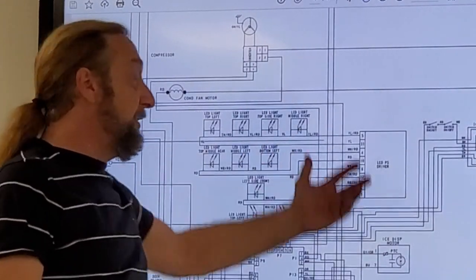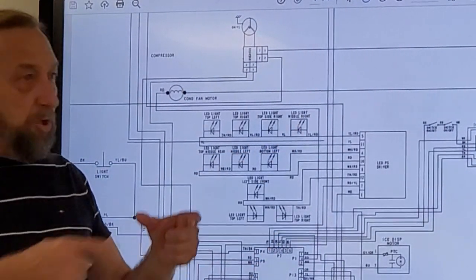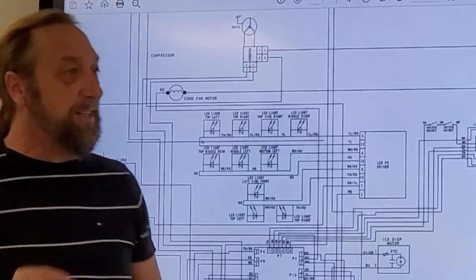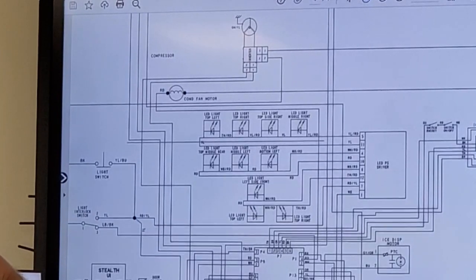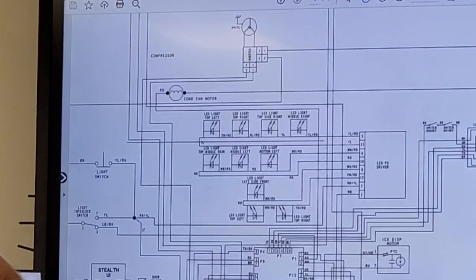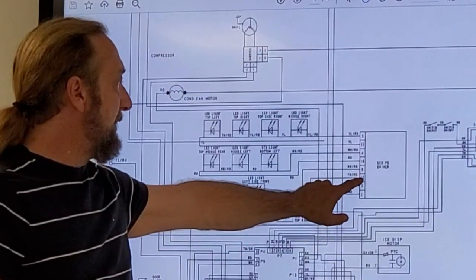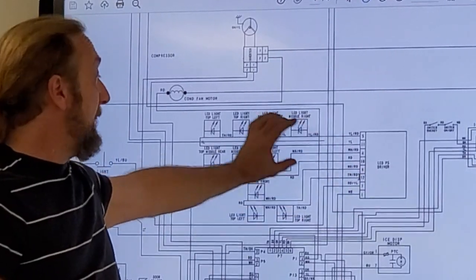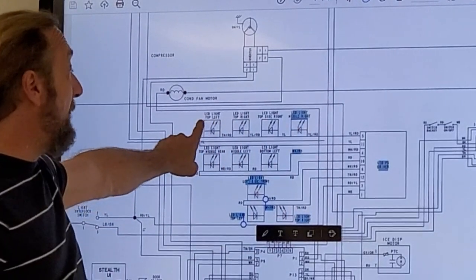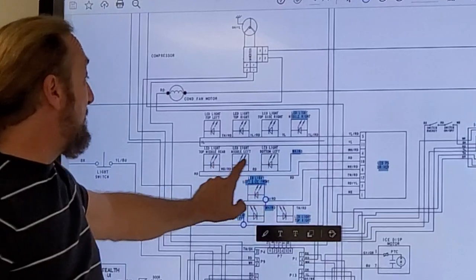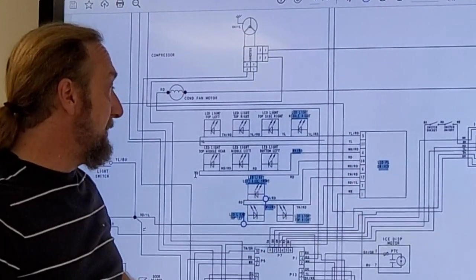So if you had no lights at all, you could have bad lights in one section. I've had customers sometimes where one light goes bad and they never call. Then another one goes bad in a different circuit, now they have no lights and they call for help. You're like, what are the odds of all those lights being bad — it's got to be a bad board, right? Or a door switch. So you go check for 120. I got 120 — okay, I'll order the driver board. So all we have to do to identify if our driver board is good or bad: check 120 in and just pick one circuit and see if we got the voltage coming out to the lights. If we have voltage coming out, our lights are the problem. If we don't have output voltage, the driver board is bad and we order the board.